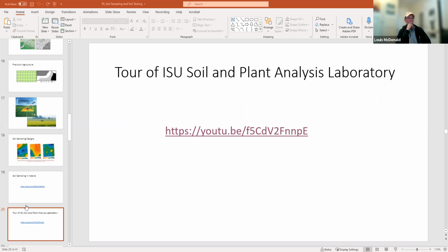The most expensive analytical instrument in the laboratory is the inductively coupled plasma atomic emission spectrophotometer, or ICP-AES unit. The operation is complex, but basically involves ionizing the sample ions by extreme heat through electromagnetic induction in an inert gas. The principle of this process is that each element emits energy at specific wavelengths peculiar to its atomic character.